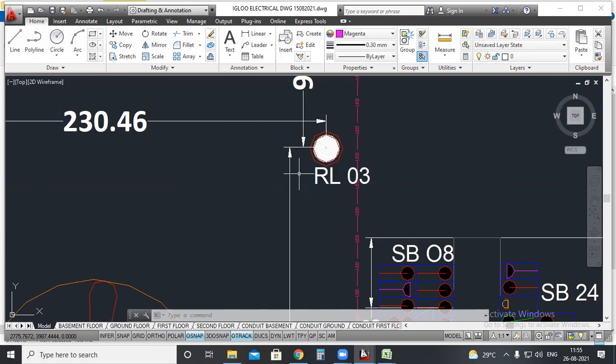That LED junction box has the provision to access these LED light fixtures, but only up to 9 watts. Even if it is concrete, you can place that LED junction box. That LED junction box will have a diameter which can accommodate up to a 9-watt round LED light. So that is also an option to provide LED recessed lights on the concrete roof.